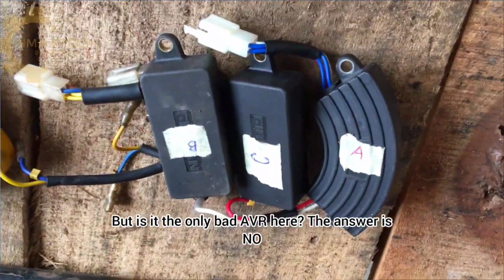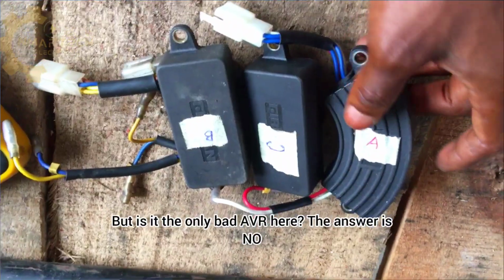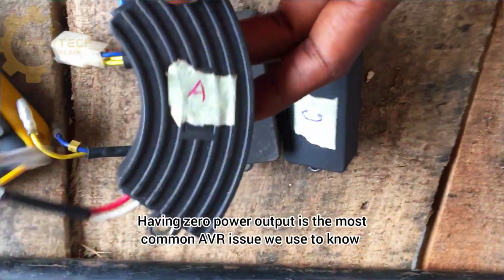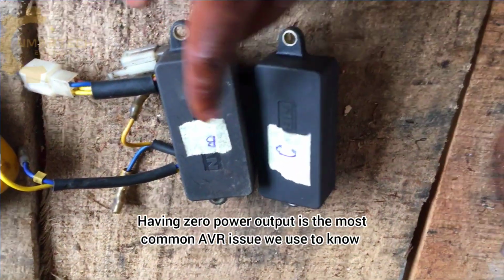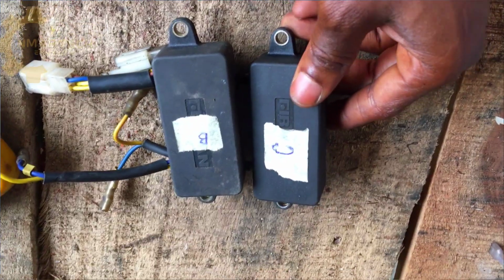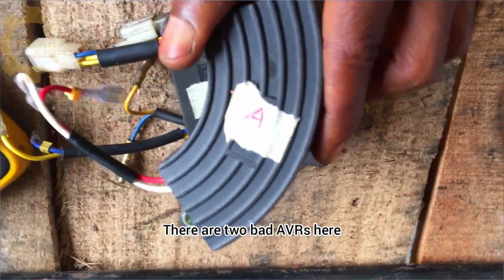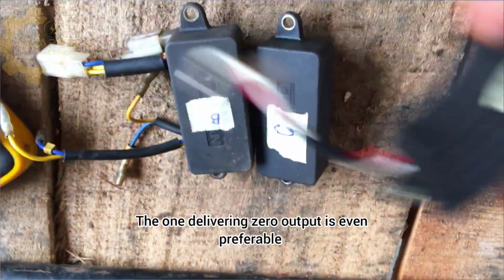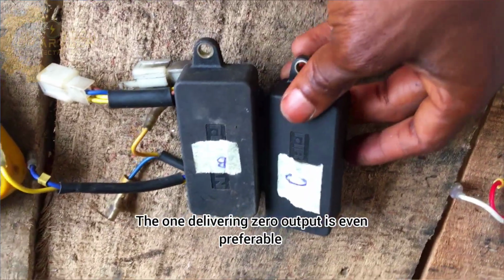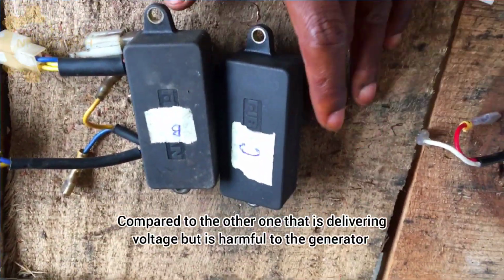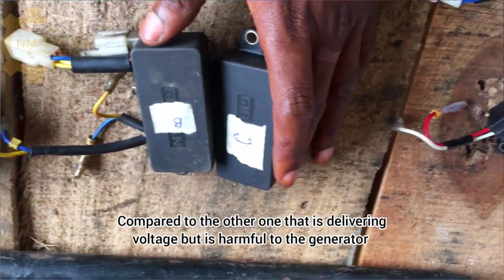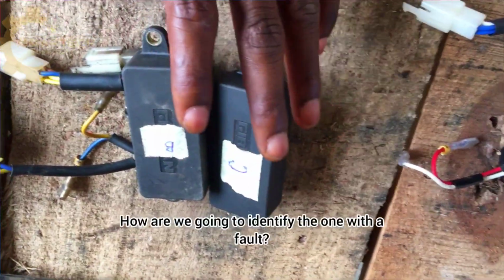But is it the only bad AVR here? The answer is no. Having zero power output is the most common AVR issue we used to know. There are two bad AVRs here. The one delivering zero output is even preferable compared to the other one that is delivering voltage but is harmful to the generator. How are we going to identify the one with the fault?